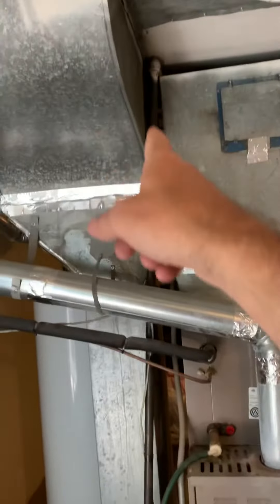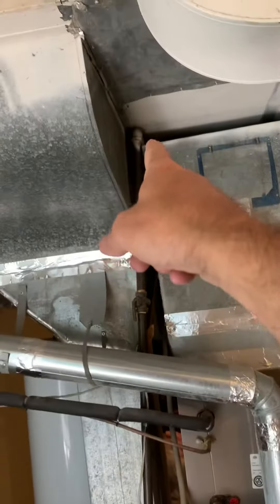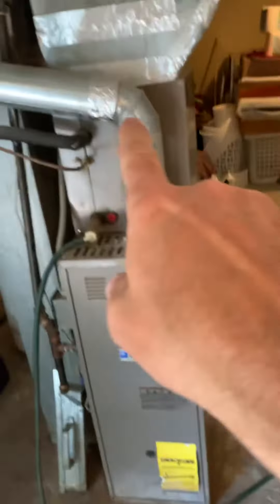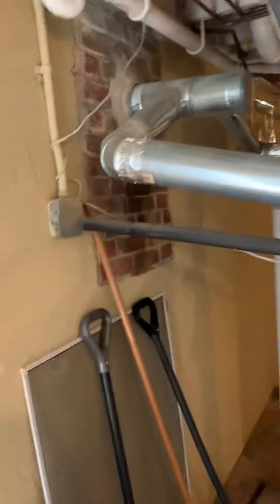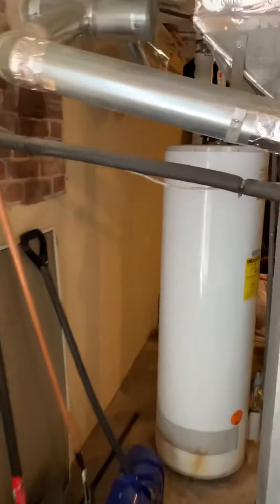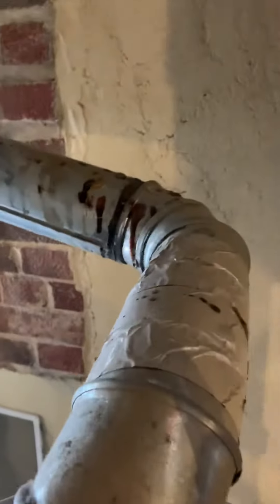For the gas piping, I think we can just get some three-quarter inch track piping, or even extend from that coupling once this is out. You can see the drain running over, hitting the floor drain. New flue piping coming up, hitting the T — we can also bring a little bit of three-inch, just replace that for them, get that all taped up. I'm not sure if there's actually anything wrong with that, but I might look into replacing that too and I'll let you know on the checklist.